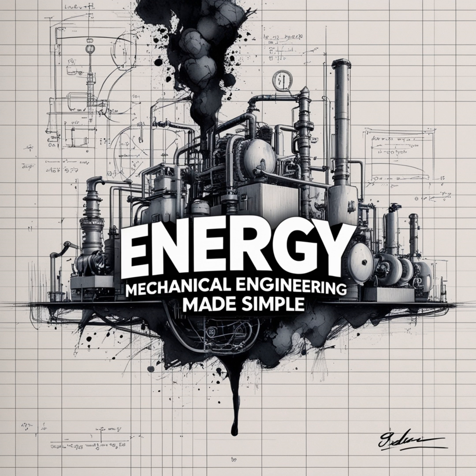And how do we calculate that required head, H_P? It comes from an energy balance on the fluid circuit. You start with something like the Bernoulli equation, but you have to add terms for all the energy losses. Losses due to friction in pipes, bends, going through the heat sink itself. Precisely. We often use the Darcy-Weisbach equation or similar methods to calculate those frictional head losses. They typically depend on the square of the flow rate. So the faster you try to push the fluid, the resistance goes up sharply.